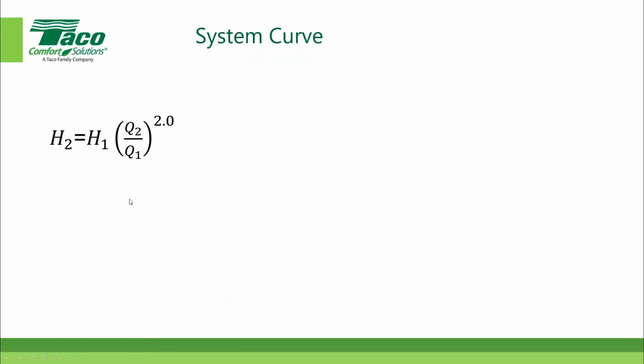There we go. Okay, so we are going to use this equation right here. If we're looking for the final pressure, in this case H2, we multiply the initial pressure times the ratio of the flow squared, the final flow divided by the initial flow, squared. In our case, we started off with 300 gallons per minute and an initial pressure of 53 feet. If we put that into a little spreadsheet format, it looks a little bit like this.